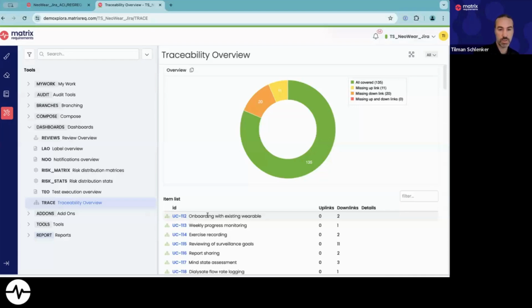And what traceability helps you to do is to make sure that everything is actually covered by test cases. So later on, if you run all your test cases, you know that you actually covered all of these requirements as well. Of course, the content is still up to you. You still need to make sure that technically these test cases do cover what they're supposed to cover, but just having this linkage between the items helps you to make sure this is actually the case and makes it easier to track these things.